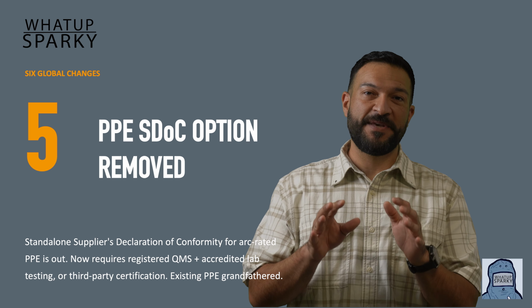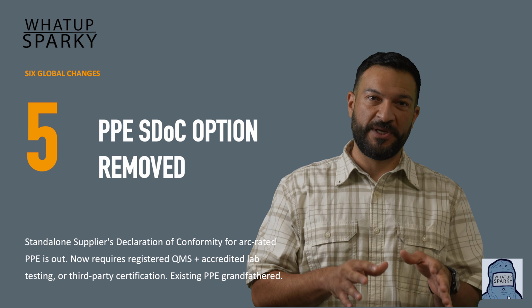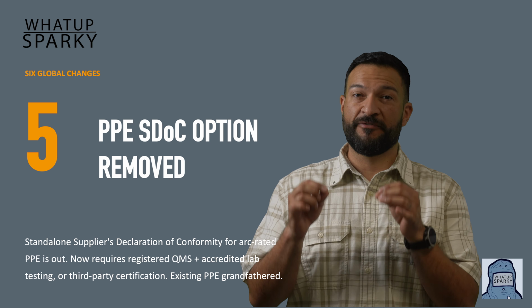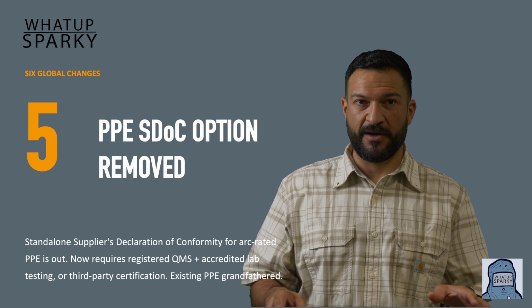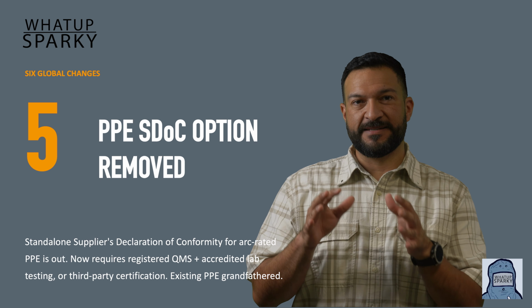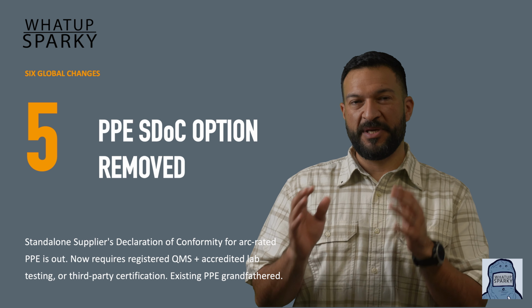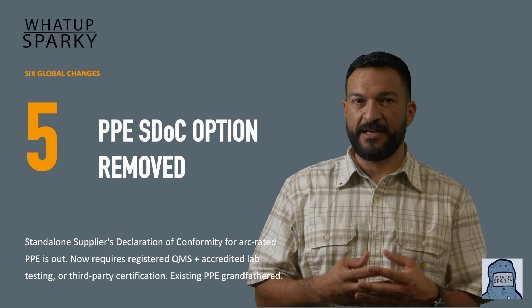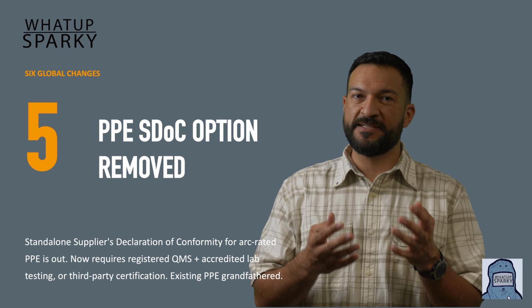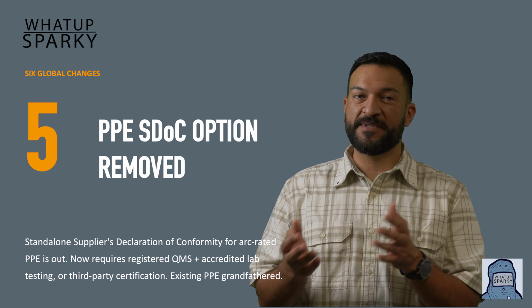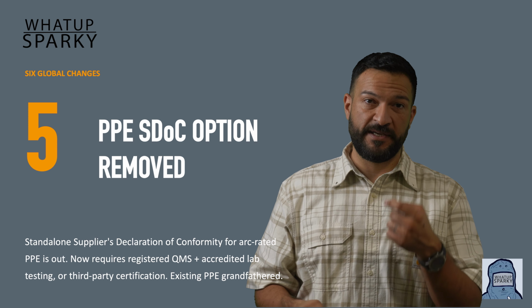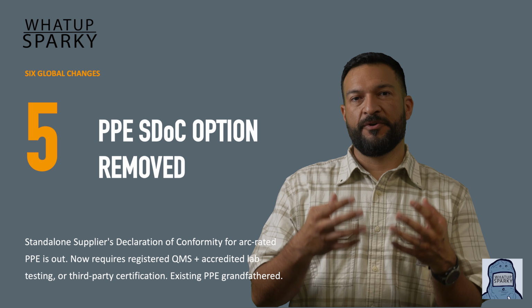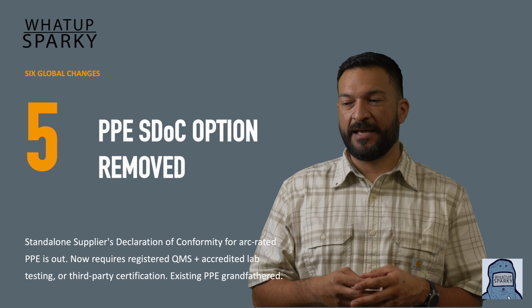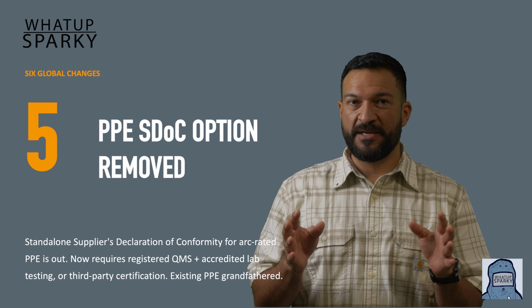Five, PPE supplier's declaration of conformity as a standalone option for PPE requirements is gone. That was deleted as a standalone option for ARC-rated PPE compliance. You now need either a registered quality management system plus accredited lab testing plus the SDOC, or third-party certification. Existing PPE is grandfathered.